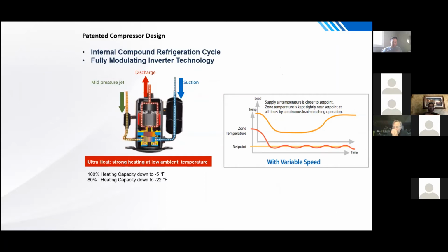But the big issue with compressors is, and those of you who are in the business and do service know all this, the compression ratio is really important. And when it's really cold outside, the suction pressure drops like a rock, which increases your compression ratio. If the compression ratio gets too high, the unit gets too hot. So in order to manage the compression ratio and therefore the heat, they've taken this mid-pressure jet, which they take off of either the discharge or the suction side, I don't know, but they do build up the suction pressure to manage this ratio and keep the heat down. And they've done a better job of it than anybody else in the world, and they've been doing it since 2012. So the output for heating in this is the highest of any product that we're familiar with.